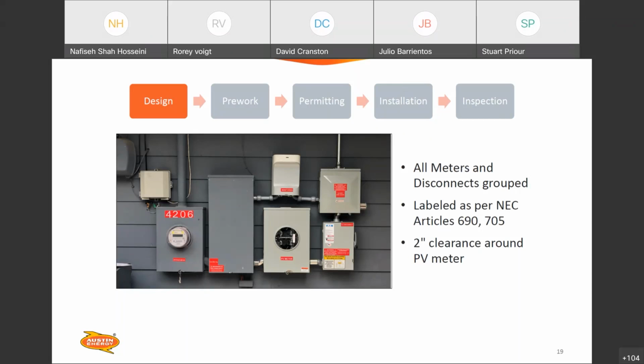Everything should be labeled as per NEC 690 and 705, but pay close attention to those two articles. There are also, above and beyond 705, some guidelines in the interconnection guide with some specific nomenclature as far as labeling goes, especially when it comes to energy storage and batteries on site. So reference the interconnection guide if you have any questions on labeling. And once again, 2 inches of clearance around the solar meter. Probably in this situation right here, you can see the billing meter may not quite have 2 inches. That wouldn't be a failure, but going forward, doing things right, let's keep 2 inches around that meter can for future serviceability. All right, next slide.